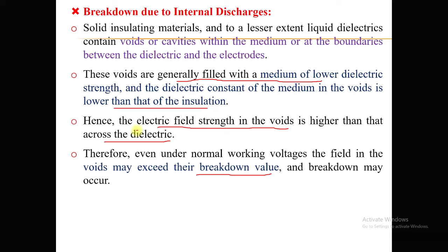So what happens when the voltage is applied? The potential gradient in the void becomes higher than the potential gradient across the dielectric material. It produces the breakdown of this void when the normal working voltage exceeds its breakdown value. Okay, so when the voltage across the cavity becomes more than its withstanding capacity, the breakdown will take place at the cavity or at the location of the weakest region. But this discharge is not bridging the gap between the two electrodes, it occurs only partially. So that is why it is known as a partial discharge.